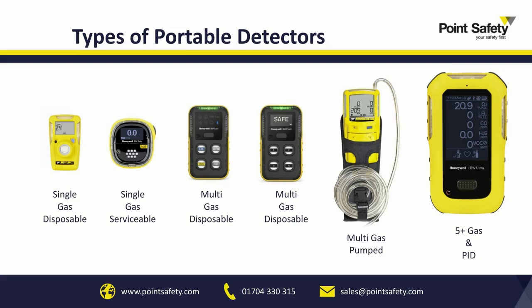We'll then move on to multi-gas disposable. A multi-gas disposable will generally be 4 of your standard sensors for confined space entry: carbon monoxide, hydrogen sulfide, a flammable sensor, and an oxygen sensor. The disposable is designed primarily for large compliance markets where they do not want charging on a regular basis, and they do not want their employees to take executive actions on it. It's a runaway meter, so if the meter alarms, they will vacate the area, so they don't need to know the concentrations being reached. They just need to know to leave the activity they're doing.